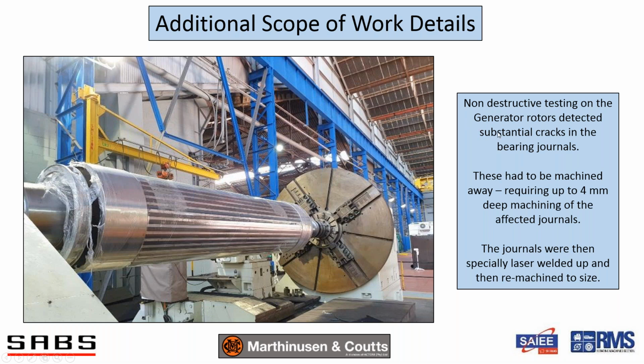So what we found, which initially was a potentially catastrophic find, is quite substantial cracks in the main bearing journals of the generators. So under careful guidance of subcontractors, metallurgical specialists, welding specialists, etc., we machined into the journals, and they were laser welded and remachined to the correct dimension. And that was a substantial additional scope, which also added time to the project.